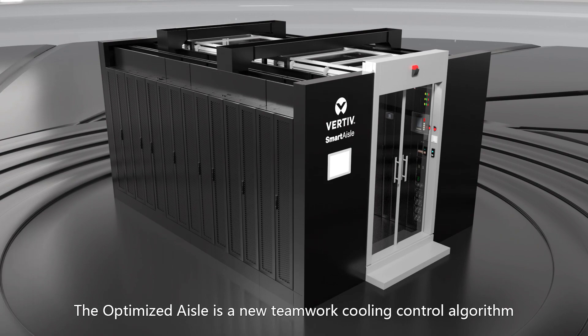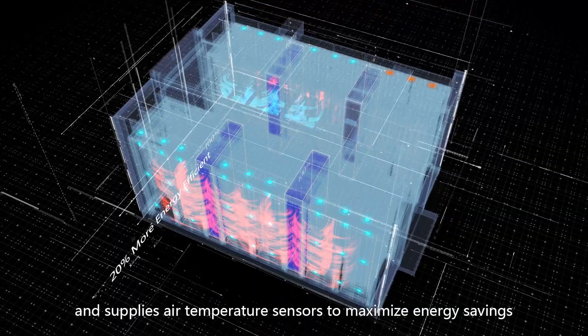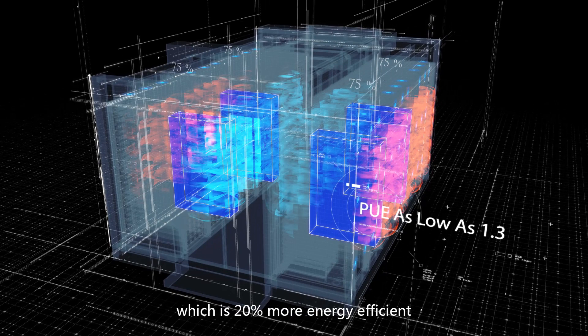The Optimized Aisle is a new teamwork cooling control algorithm that uses remote rack temperature sensors and supply air temperature sensors to maximize energy savings. Optimized Aisle controls air volume and cooling capacity separately, which is 20% more energy efficient.